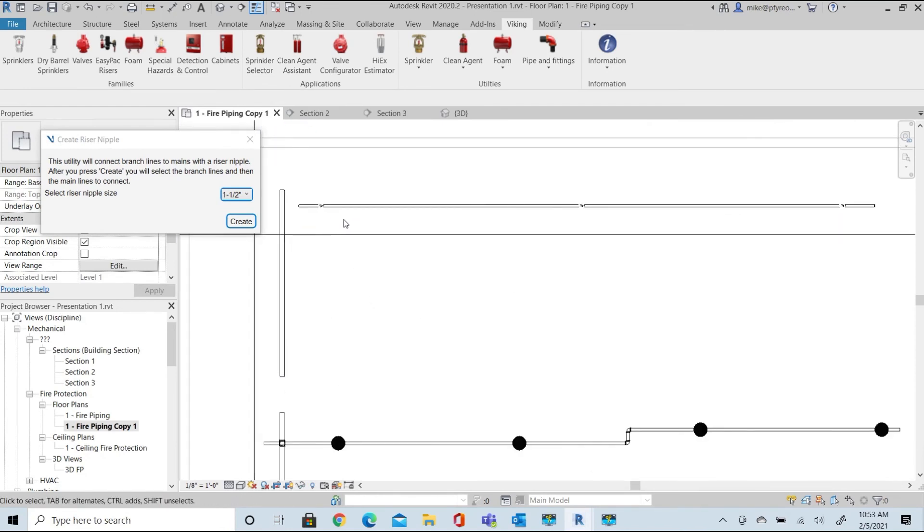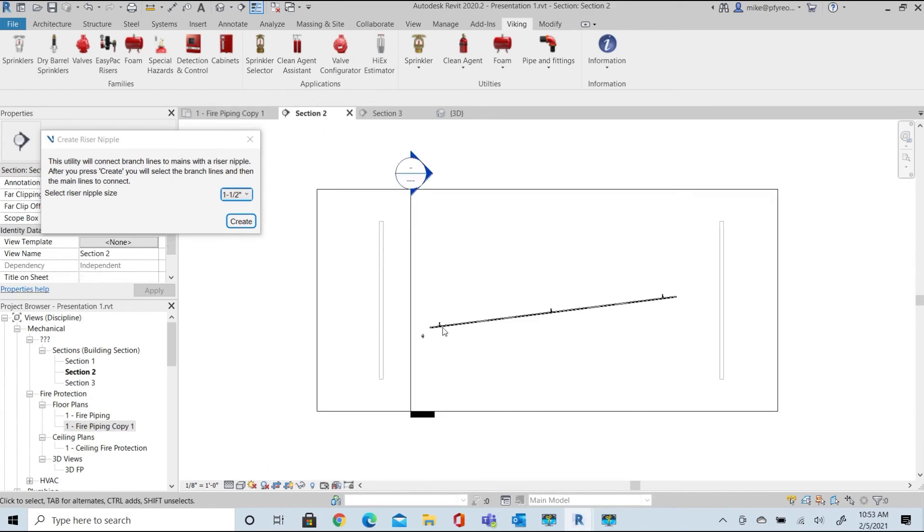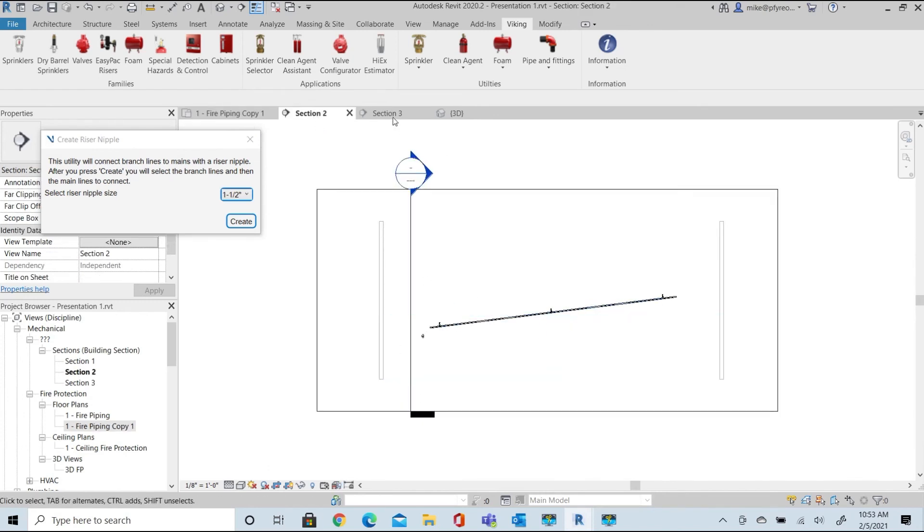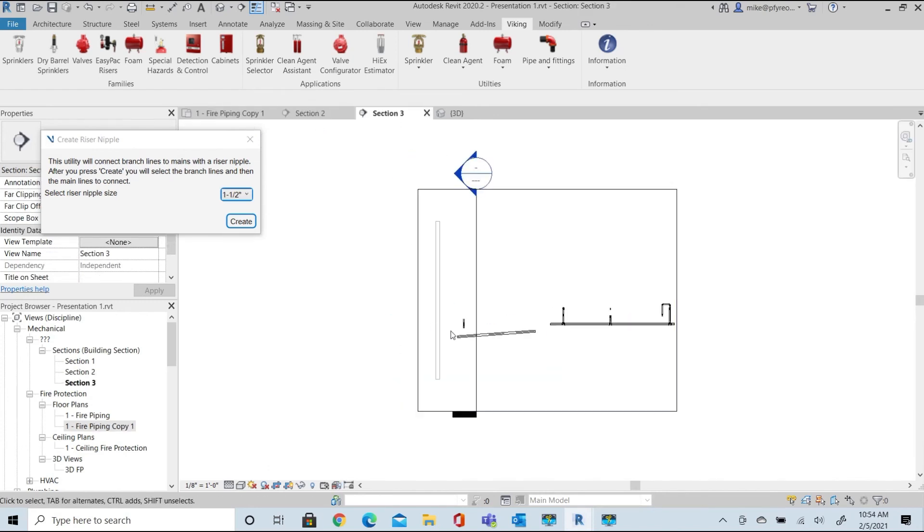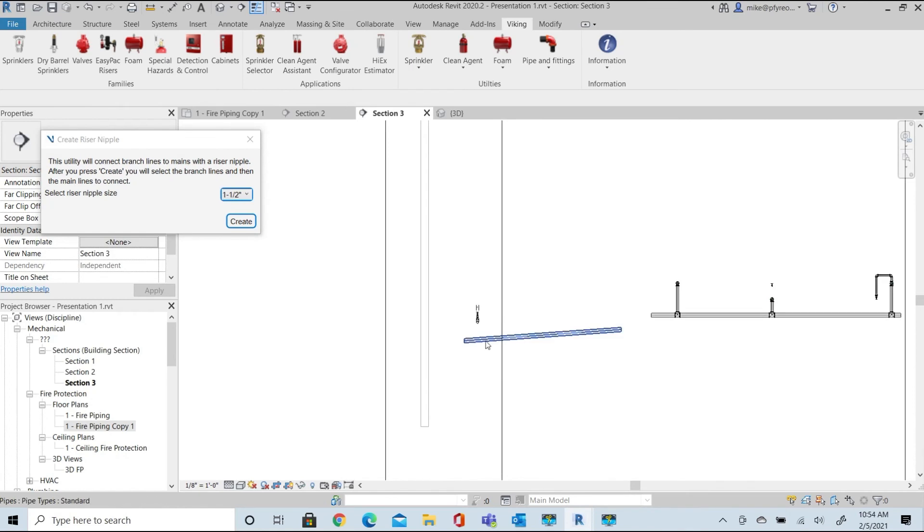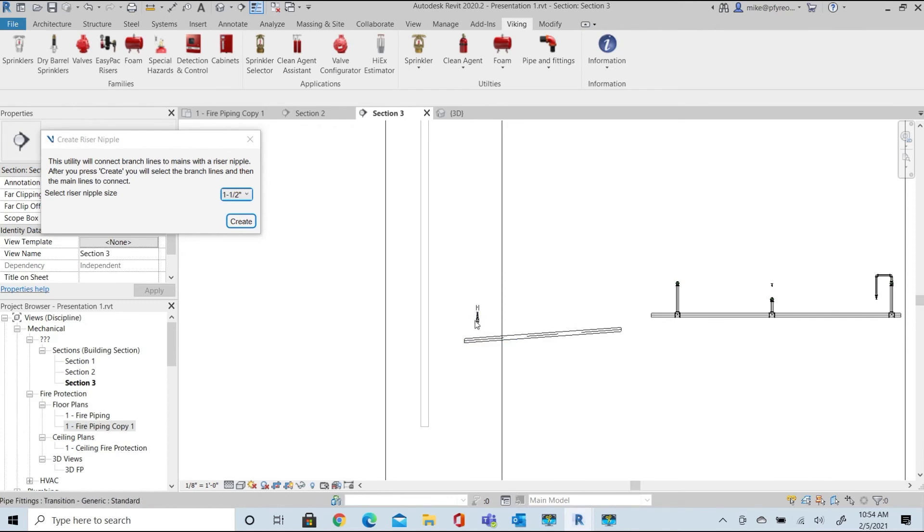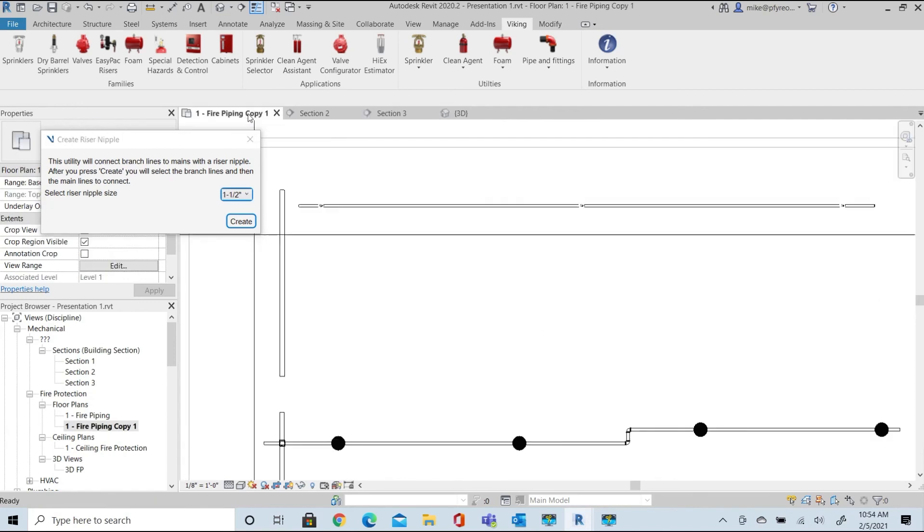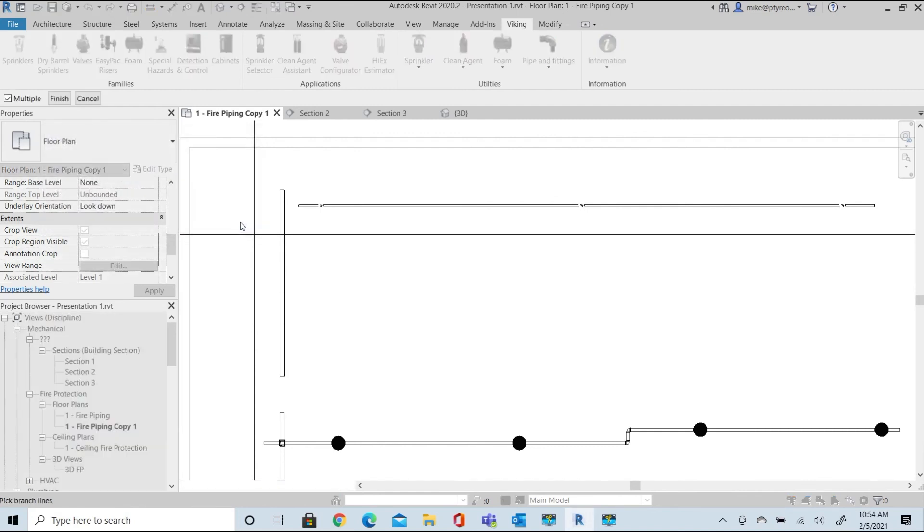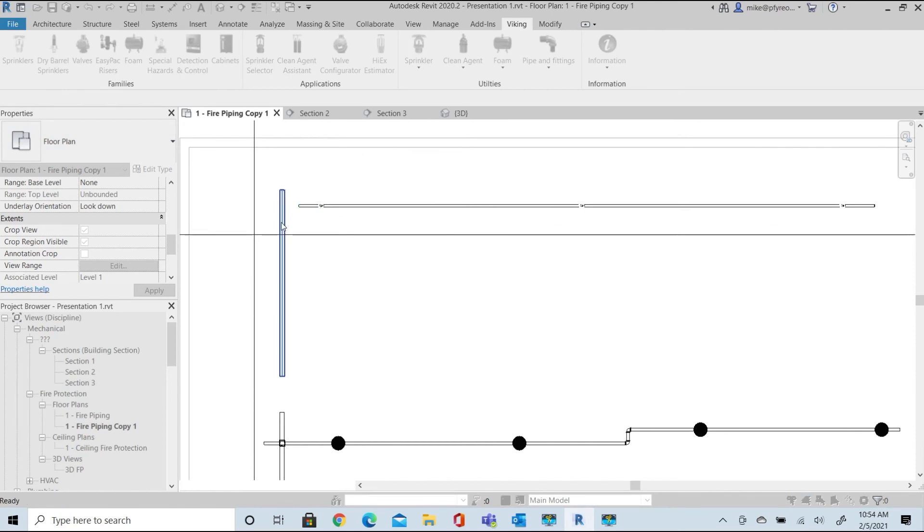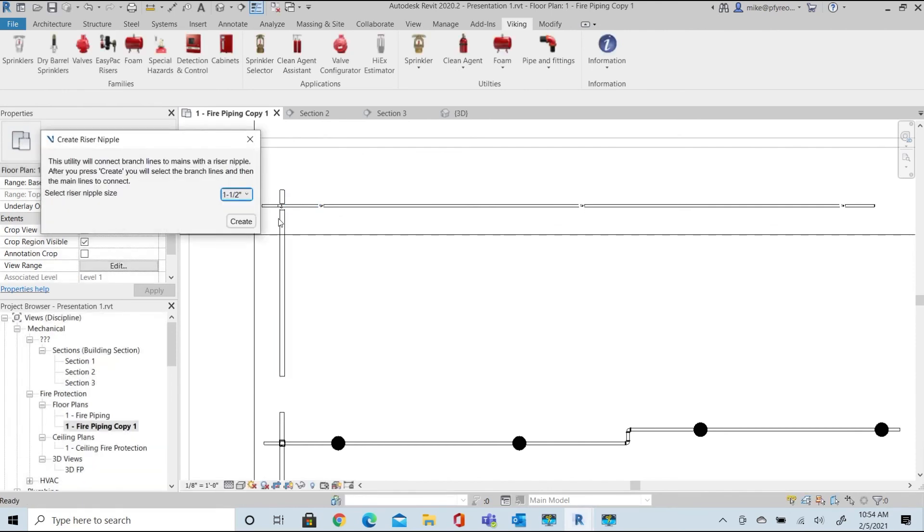Another common riser connection issue is with sloping pipe. In this example, we have a double slope. The branch lines are sloped in one way, and the cross main is also sloped, creating opposing slopes. This is a very difficult operation to perform in standard Revit piping connections just using the system and pipe tools. This routine makes this connection very simple. It calculates all of the necessary intersection points and angles, and connects the pipe appropriately.